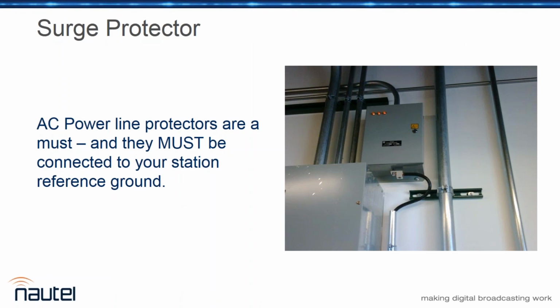I second what you said about impedance with the surge protector. When the surge protector fires, it's a very low impedance short, which is what you want it to be. But you have to seriously think about the impedances of both the hot and ground wires, from where the surge hits to past the surge protector, or it can affect your transmitter. You want to make the impedance, which is more than just DC resistance, it's the impedance to the steep wavefront of the surge, to ground as low as possible at that point. Ground here means the common ground for the whole site.